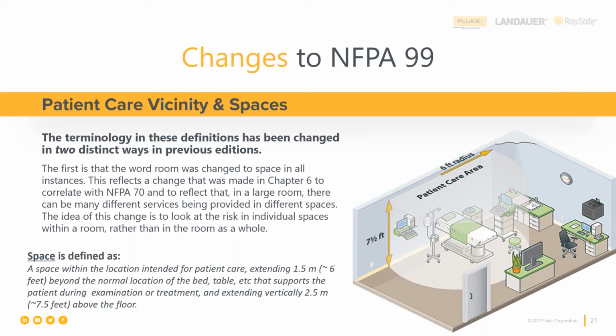And you'll note in the picture we're measuring from the floor 7.5 feet up from the floor and in a 6-foot radius of each patient treatment area. So that's when measurements need to be made. These are the areas where you need to document specific measurements and where in the room the medical device is located.